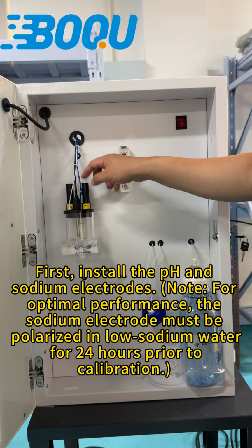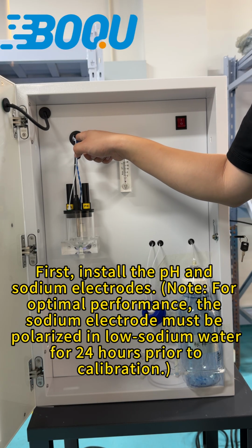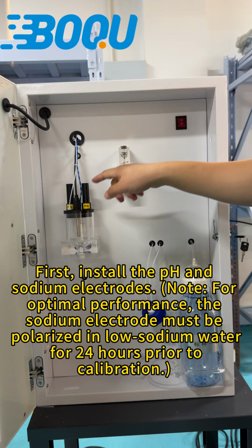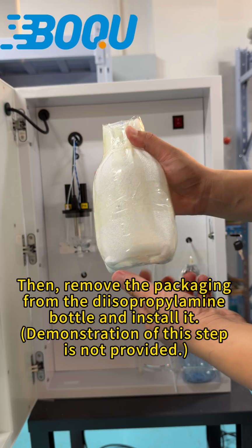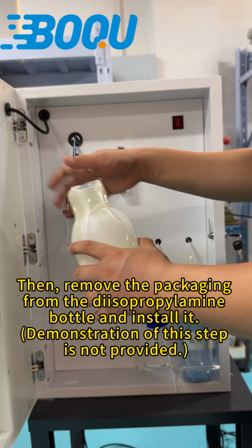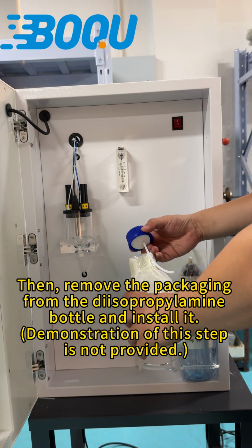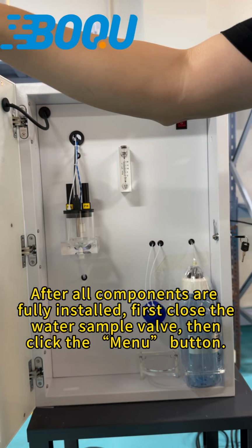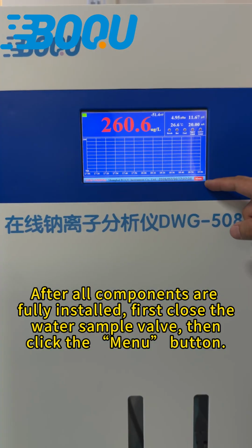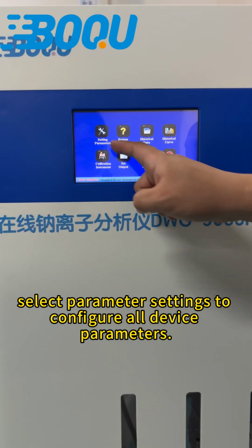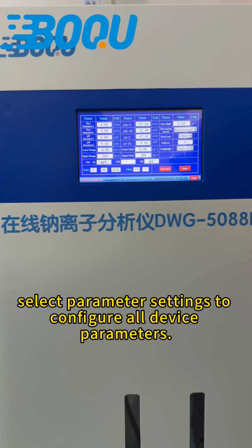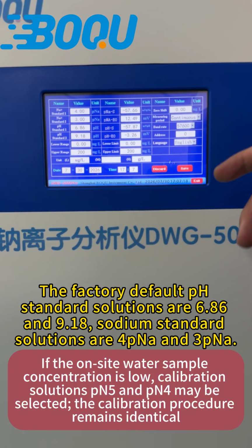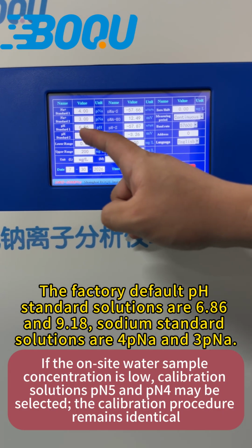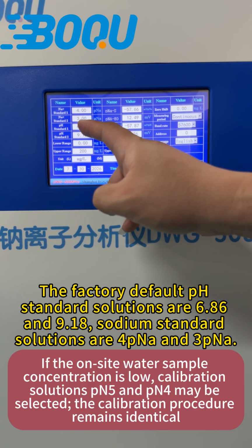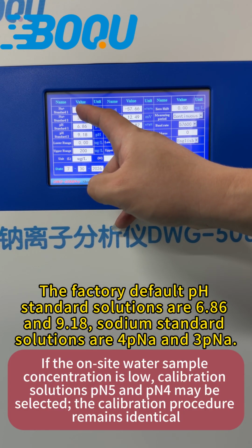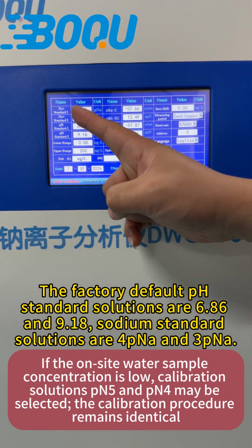Note, for optimal performance, the sodium electrode must be polarized in low sodium water for 24 hours prior to calibration. Then, remove the packaging from the diisopropylamine bottle and install it. Demonstration of this step is not provided. After all components are fully installed, first close the water sample valve, then click the Menu button. Select Parameter Settings to configure all device parameters. The factory default pH standard solutions are 6.86 and 9.18. Sodium standard solutions are 4 pNa and 3 pNa.